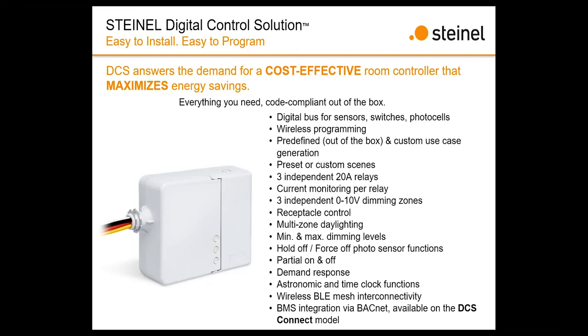You can have multi-zone daylighting. You can adjust the minimum and maximum dimming levels, partial on, partial off, demand response if that applies to your case, astronomic and holiday time clock, and wireless BLE mesh interconnectivity between the devices to remove the need to wire up all the devices to a central hub or to each other.